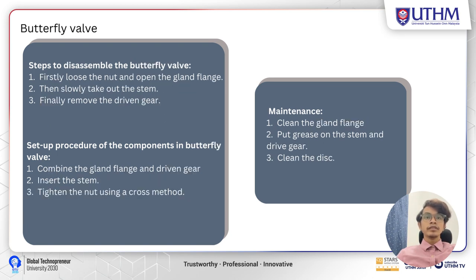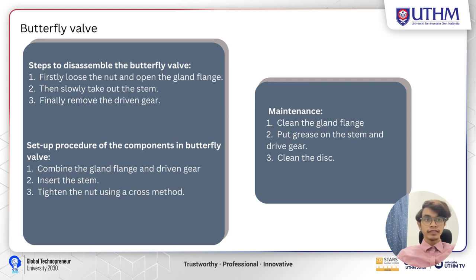For the butterfly valve, the steps to disassemble are: loosen the nut and open the gland flange; slowly take out the stem; and finally remove the driving gear. To reassemble: combine the gland flange and driving gear; insert the stem and tighten the nut using a cross method. For maintenance, clean the gland flange, put grease on the stem and drive gear, and clean the disc.